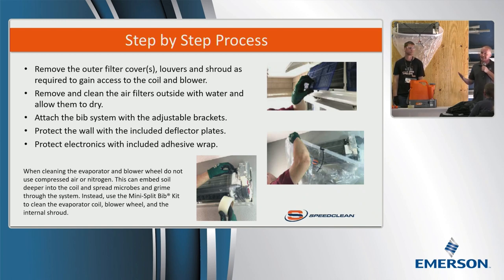Maintenance cleanings, in a lot of cases, you're not even going to use a cleaner - water is fine. Generally speaking, for a condenser, you use water, especially in the age of microchannel, where you really want to follow the manufacturer's instructions, and generally manufacturers are telling you never use cleaner at all. Some will give exceptions for very mild cleaners, but aluminum is not tolerant to highly alkaline cleaners - it just doesn't do well, and you will damage them very quickly. With microchannel, the walls are super thin. So it really depends on the application, but for maintenances, I'd suggest water, a very mild cleaner, or a typical cleaner highly diluted.